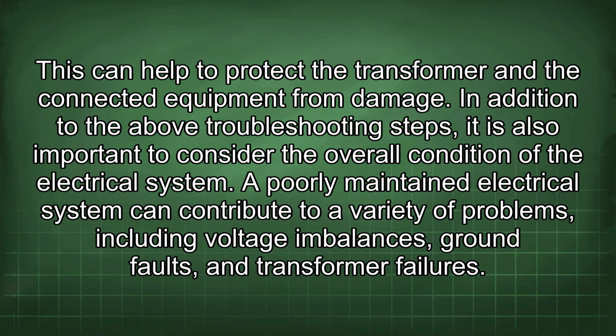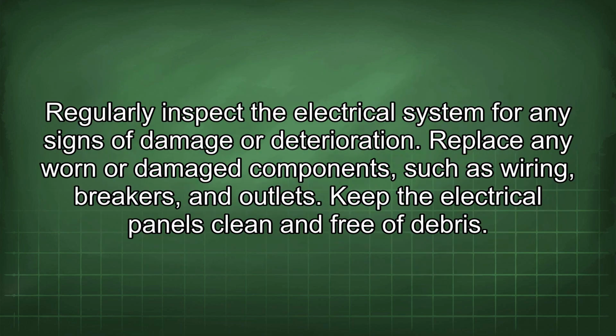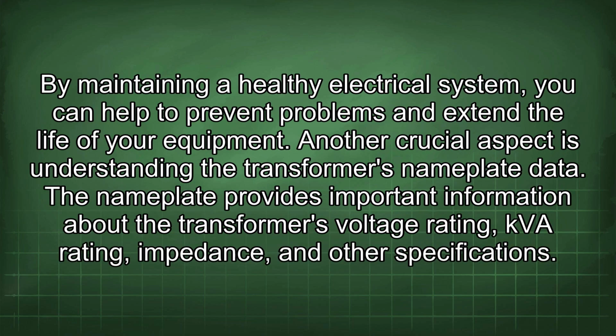In addition to the above troubleshooting steps, it is also important to consider the overall condition of the electrical system. A poorly maintained electrical system can contribute to a variety of problems, including voltage imbalances, ground faults, and transformer failures. Regularly inspect the electrical system for any signs of damage or deterioration. Replace any worn or damaged components, such as wiring, breakers, and outlets. Keep the electrical panels clean and free of debris. By maintaining a healthy electrical system, you can help to prevent problems and extend the life of your equipment.